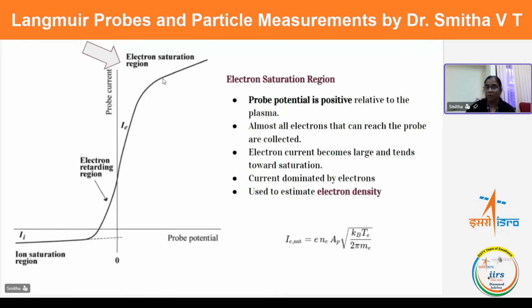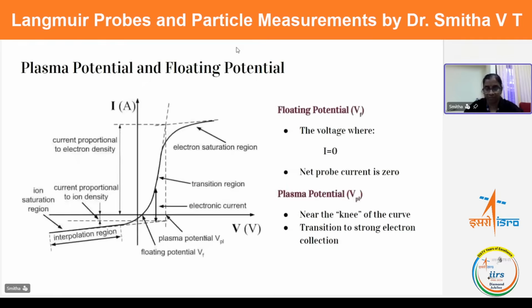Now, when we go further positive, we reach the electron saturation region. Saturation means almost all electrons have reached the probe and the probe current is collected. No more electrons will come, so the electron current becomes constant, which means the current is dominated by electrons and no more electrons are available. Almost all electrons in the medium have reached the probe. So this can be used to determine the electron density, but the expression also has the electron temperature. So when we have measured the electron temperature in the electron retardation region, that temperature goes into this expression, and the electron density can be estimated. There are other ways also to determine electron density, which will come in a moment.